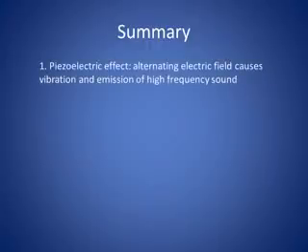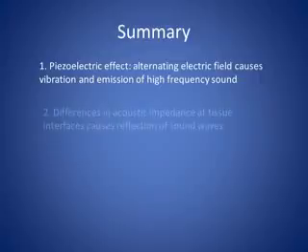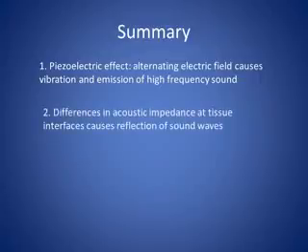To summarise these two fundamental principles, the piezoelectric effect describes how substances, including crystals, vibrate within an alternating electric field, producing high-frequency sound waves. Differences between acoustic impedance of different tissues cause reflection of ultrasound waves at tissue interfaces.